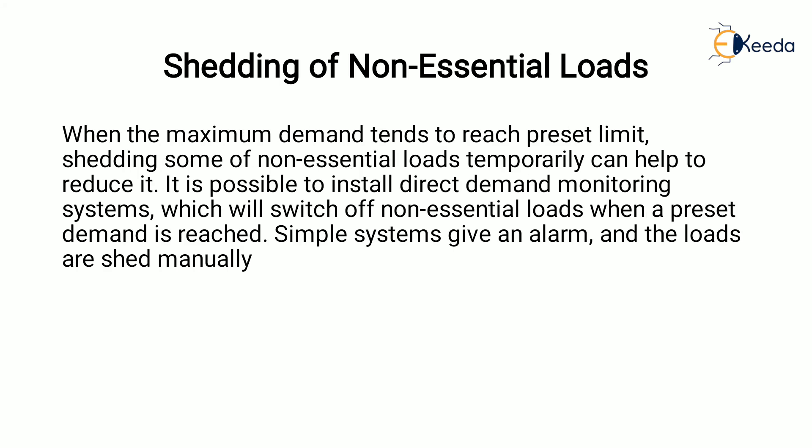Next is shedding of non-essential loads. When maximum demand tends to reach a preset limit, temporary removal of some non-essential loads can help to reduce the maximum demand on the system. It is possible to install a direct demand monitoring system which will switch off non-essential loads when a preset demand is reached. A simple system gives an alarm and the loads are shed manually. Alternatively, a maximum demand controller can be installed which will remove loads in a particular sequence and then switch them back on once the system is within limits.